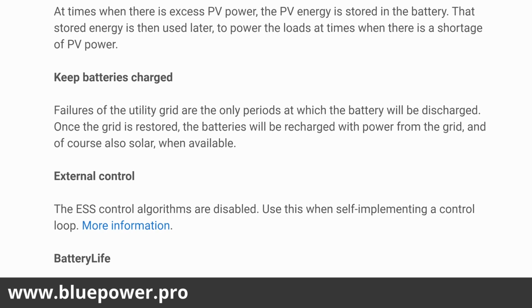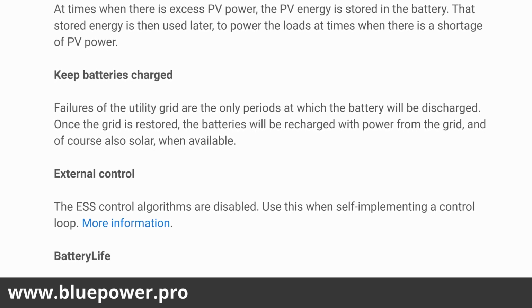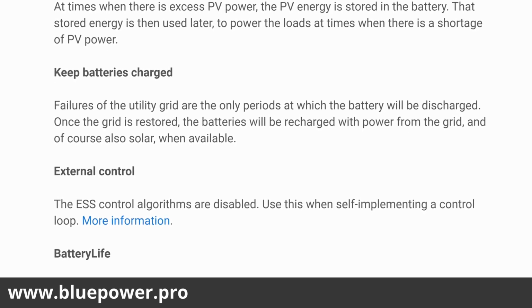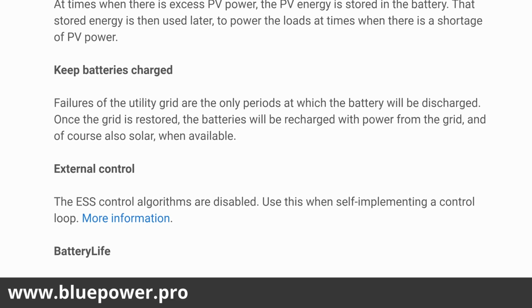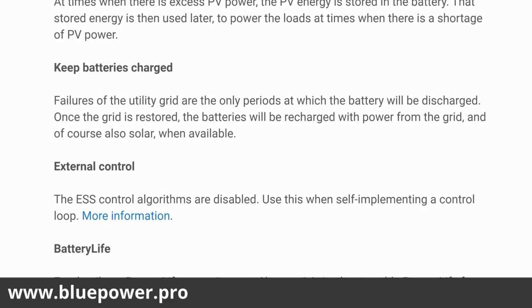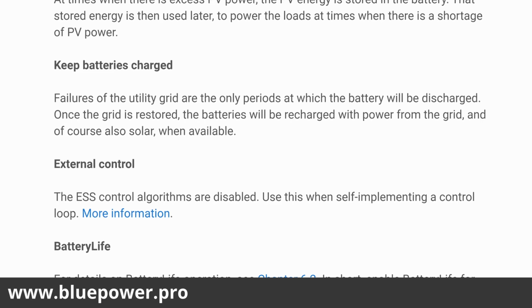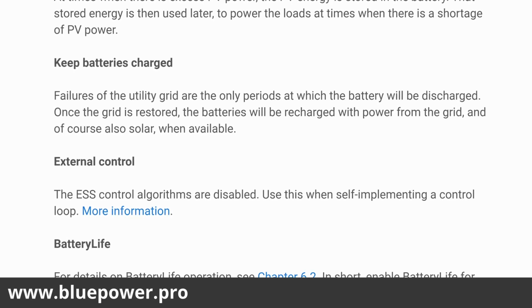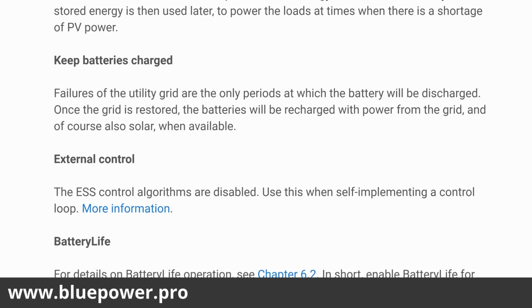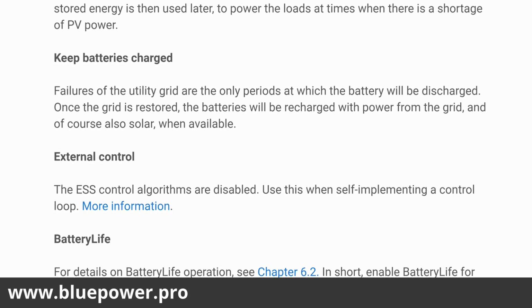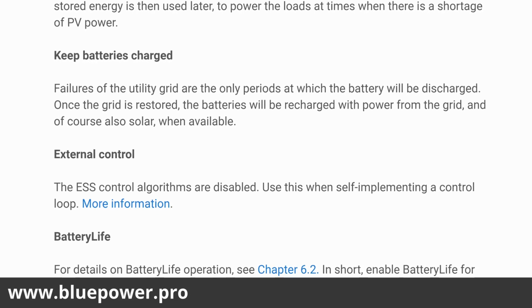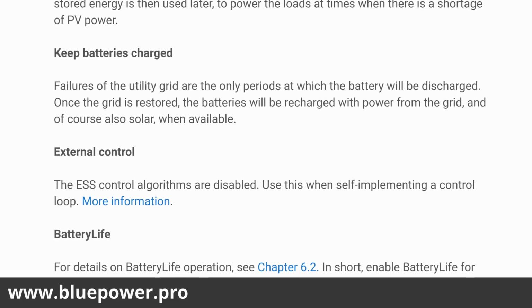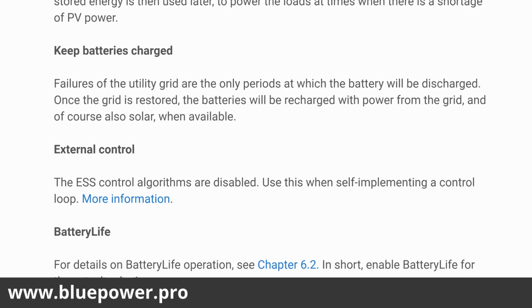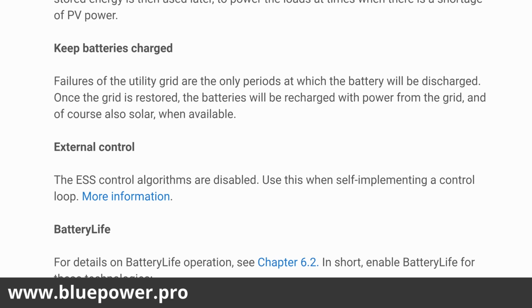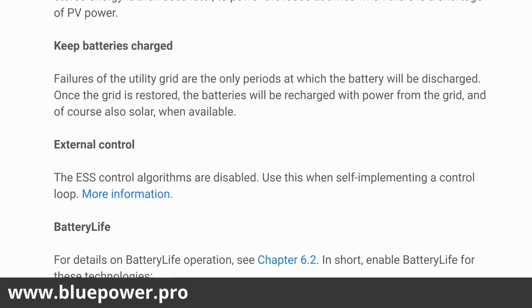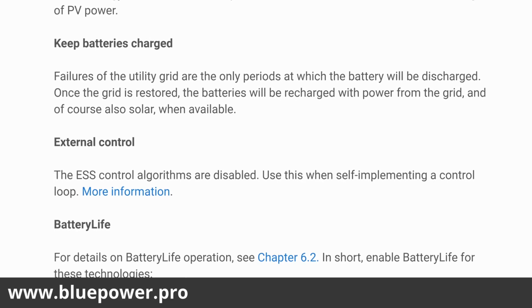But if you only produce 5 kilowatts of excess PV for the day, the algorithm will automatically notice that you only charged your battery with 5 kilowatts over the past 3 days. So your PV production is 5 kilowatt hours. Then the algorithm will automatically increase the active SOC limit to 50% in this instance, because you only have 5 kilowatt hours available to charge into your 10 kilowatt hour battery.